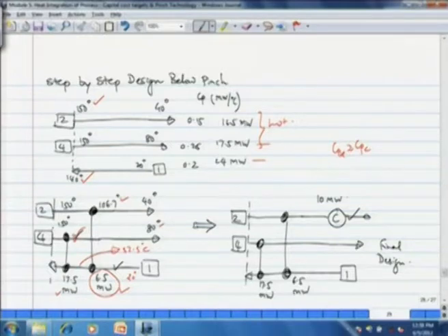And now we don't have any cold stream left because there was only one cold stream below pinch region which had a heat requirement of 24 megawatt, which has been met, 17.5 megawatt from stream 4, 6.5 megawatt from stream 2. So stream 1 is now ticked off.